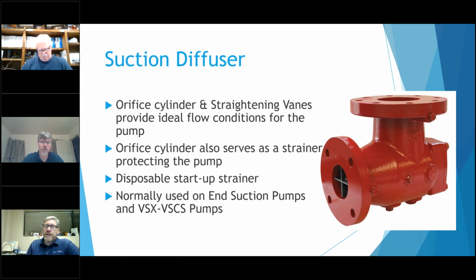What the suction diffuser does, you can see this little crosshatch right in here. There's a straightening vane in there, and it kind of evens out that flow as it hits it. There's also an orifice cylinder inside, so it spreads it all the way around the straightening vanes, and it gives you that flow condition going into the pump. So it just adds length, longevity to the pump, and allows it to work a lot less and with a lot less stress on the pump.